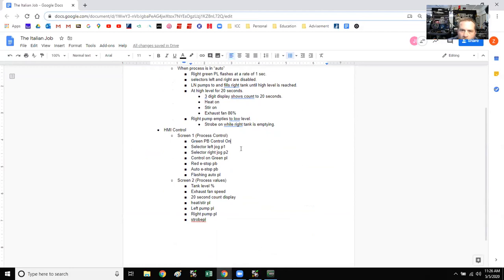So we need to edit our process and add something in parallel with the green push button. Then we're going to have a B3 for the HMI. So the B3 will become true when the HMI button is pushed, and it will turn the control on the same way the process behind us does. Does that make sense? Yeah. Yep. So we are going to use the HMI then.